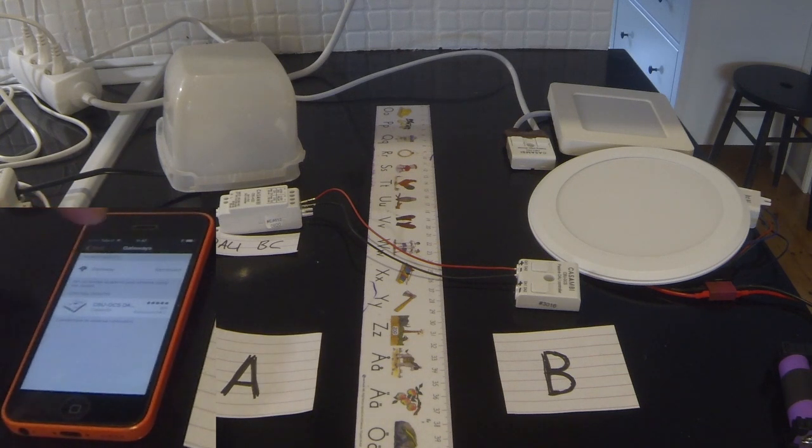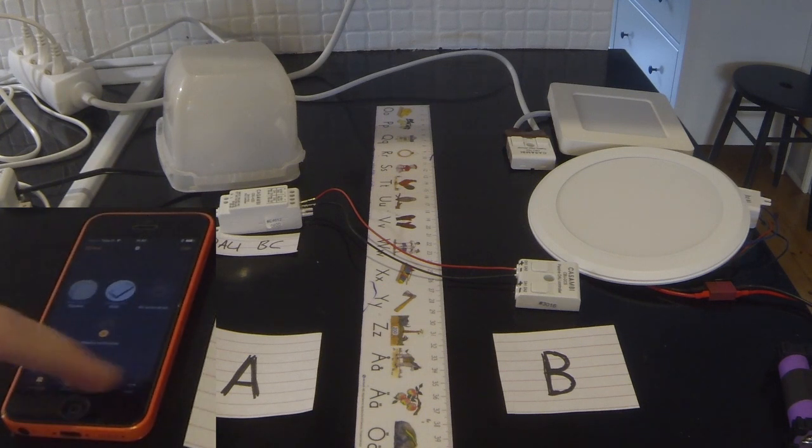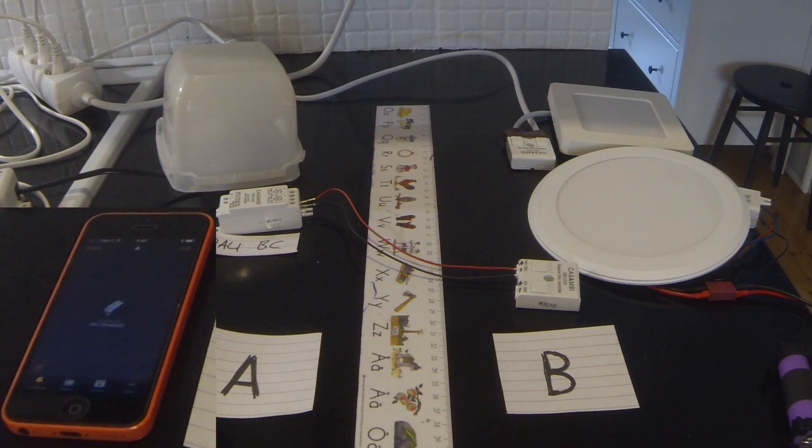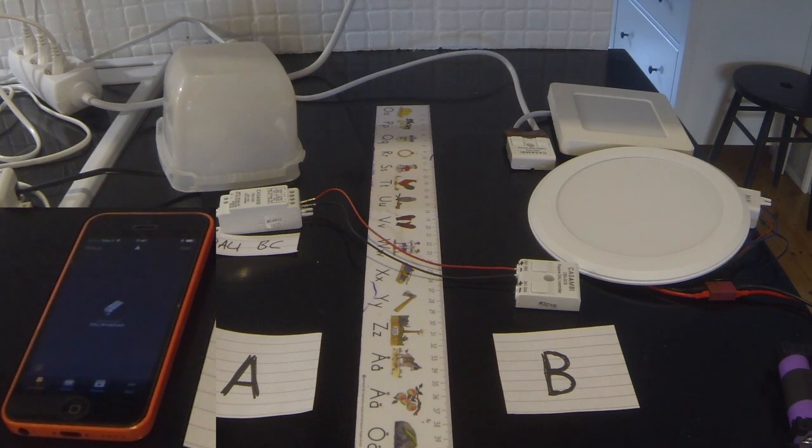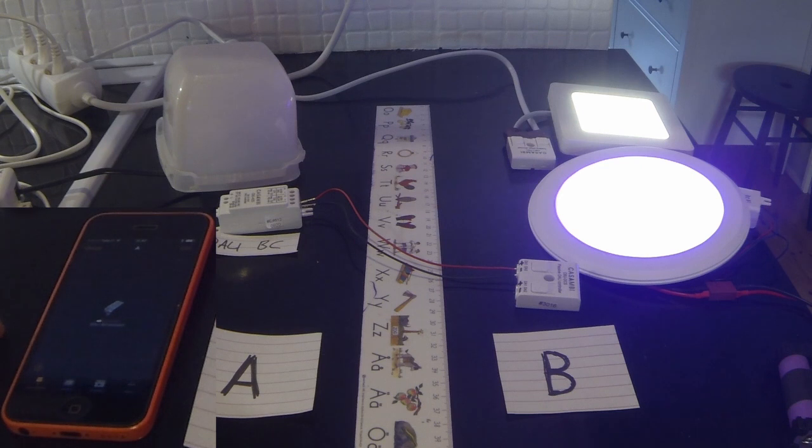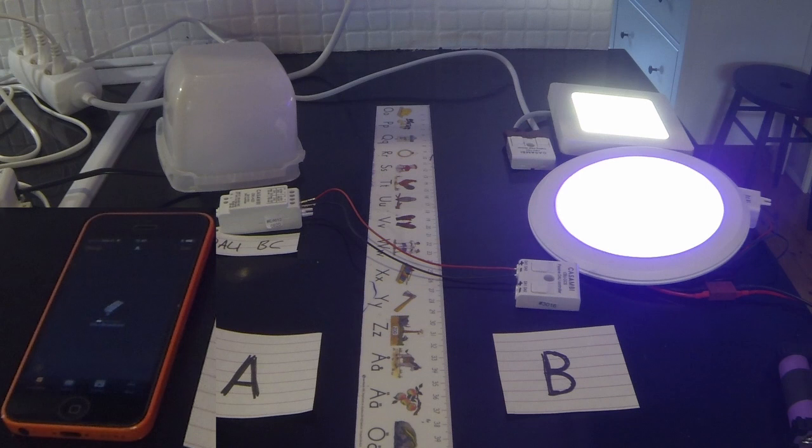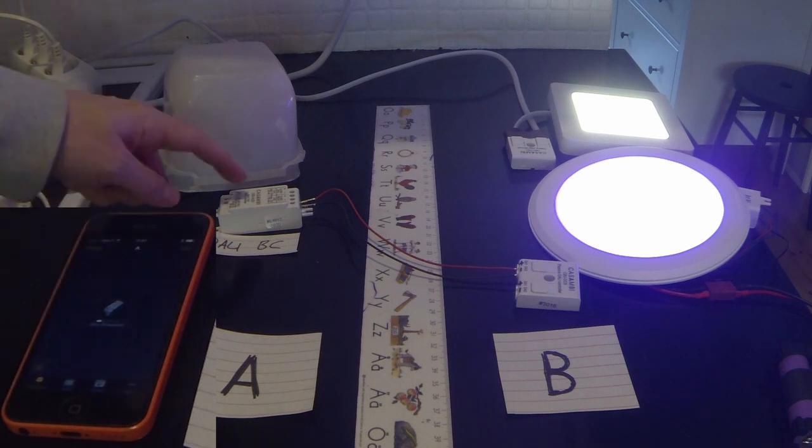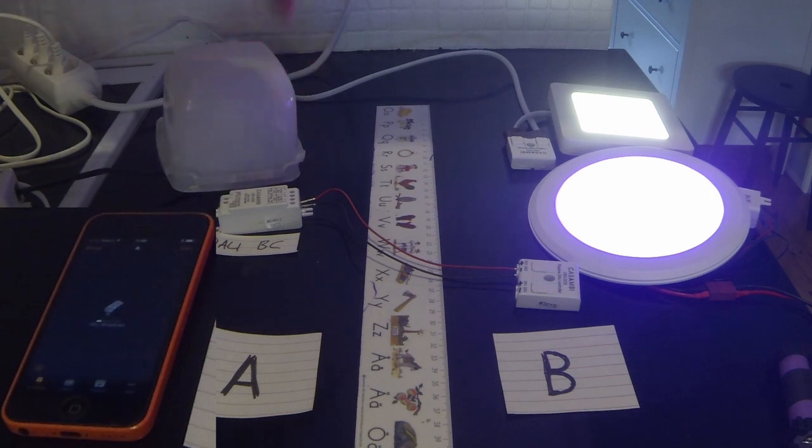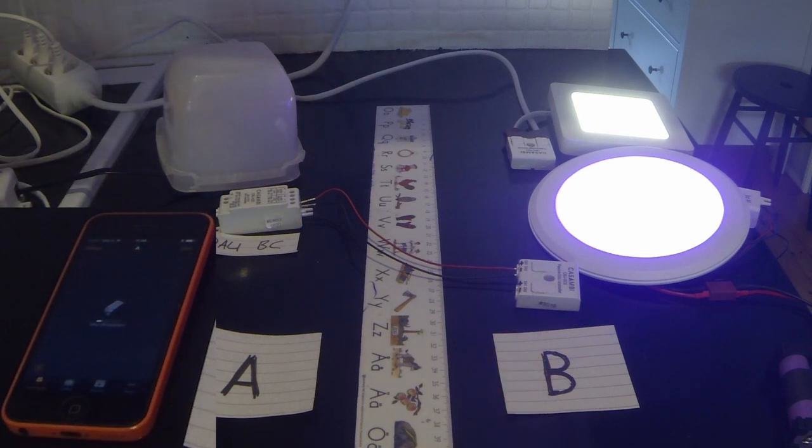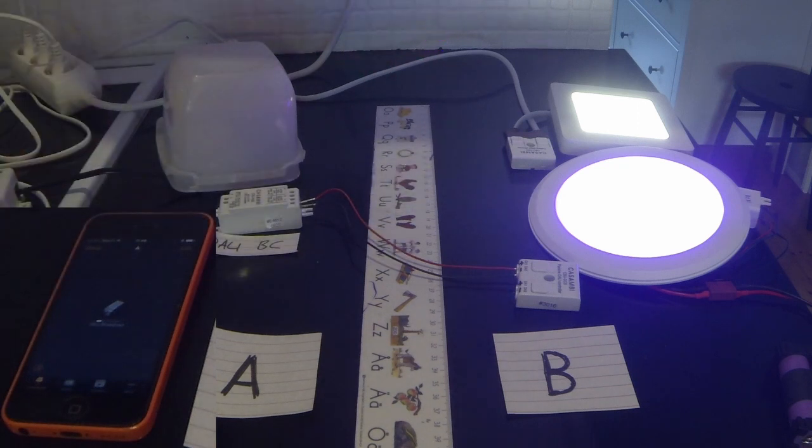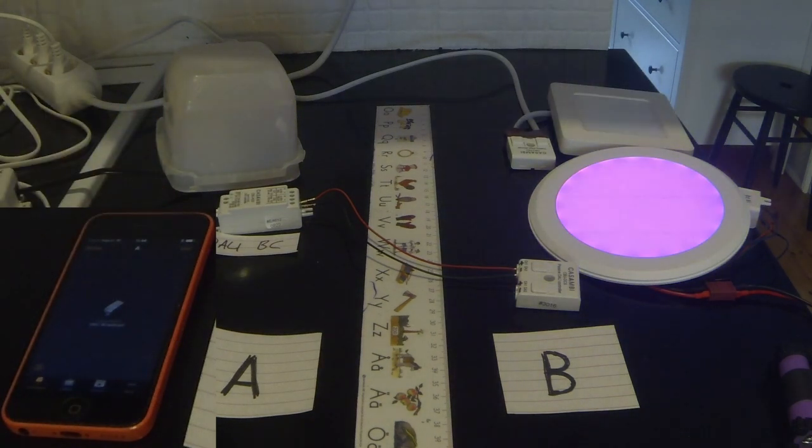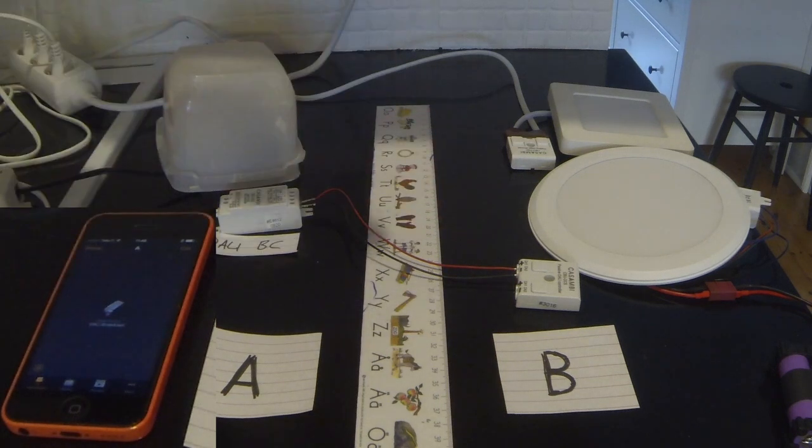So, moving back to network A, if I toggle on DALI broadcast, looks like I've got remember last state enabled, which I didn't realize. So it's dimmed to roughly 11, 10 percent. Which is actually ideal because if these lights are so bright they will overexpose and then the camera will try to compensate. So what's happened there is I toggled this light, this device on. Normally there would be an LED driver attached to it which would then power on the lights, but because I'm using the DCS gateway, DALI gateway, that same power on signal has been translated to the other network to turn these lights on. So if I now toggle this device back off, you see that it sent another signal down those wires to say turn off.